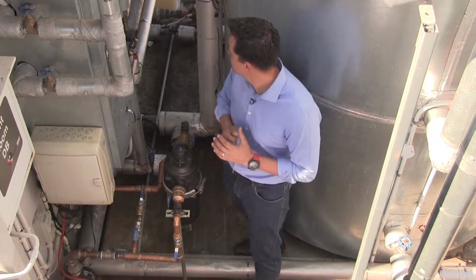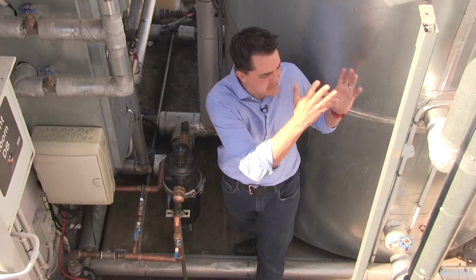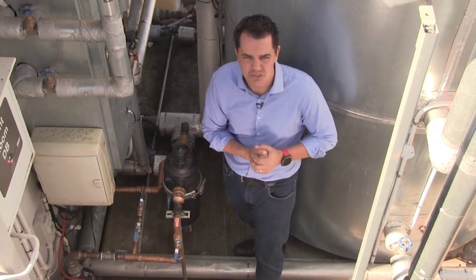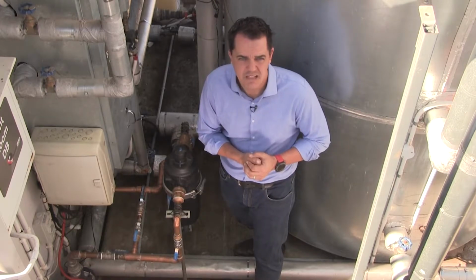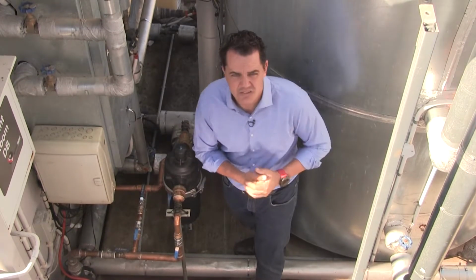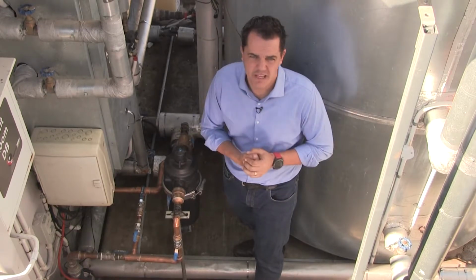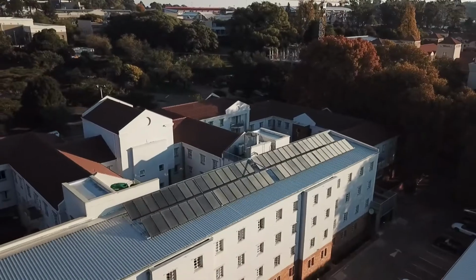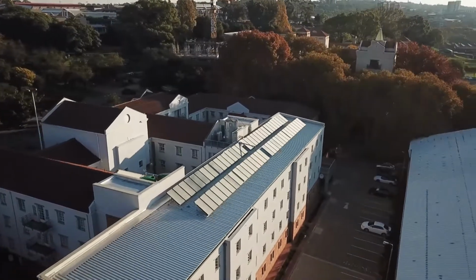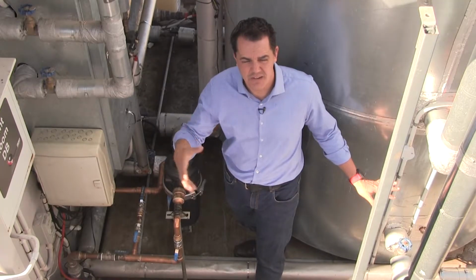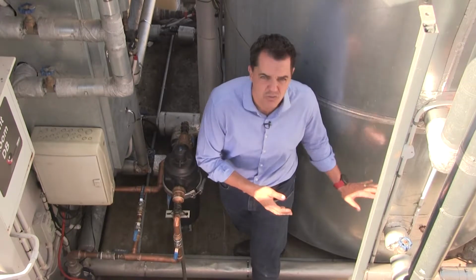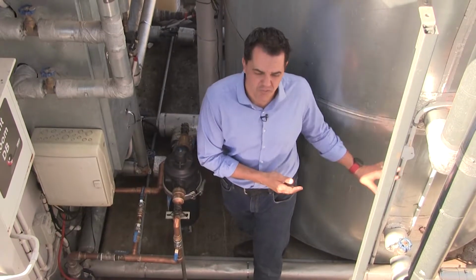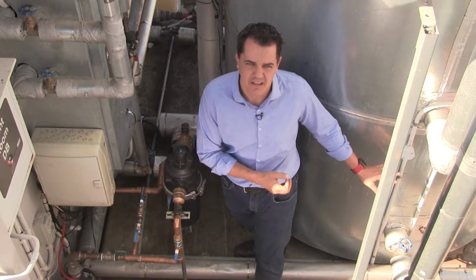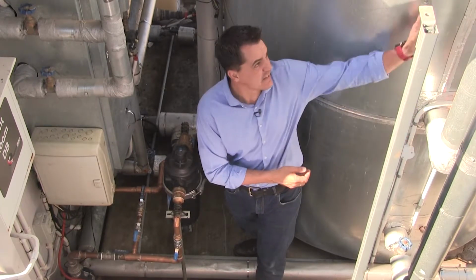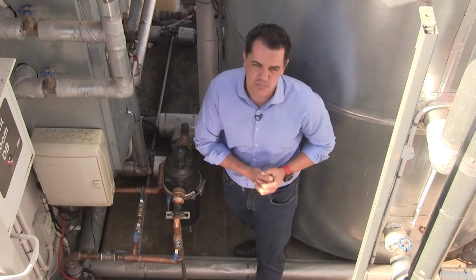The capacity of these Rinnai burners is such that they can heat this entire 10,000 litre storage tank within 2 hours. And you can see that it's positioned only at the top half. The logic for that is we've got an entire solar plant, so the solar plant must have a buffer capacity so that during the day we can load all that solar hot water energy into the bottom half of the tank, in fact charge the whole tank, and then the thermostat regulates that at any point we've got hot water in the top section of the tank.